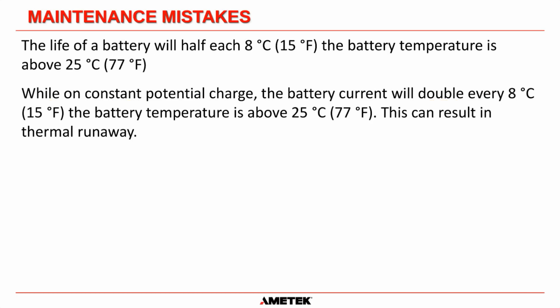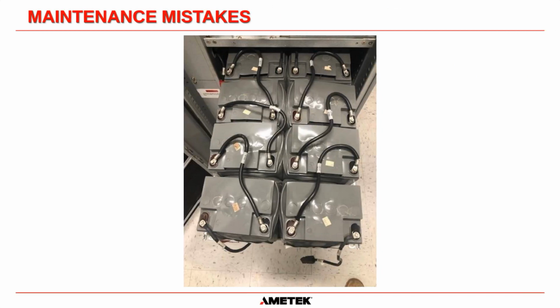And we couldn't find a really good picture of thermal runaway, because usually the batteries are destroyed. But you can see quite clearly here, these valve-regulated lead-acid batteries have swollen a huge amount. What happens is these were going into thermal runaway. The insides were heating up so much, causing pressure and causing the plastic to melt and the jars to expand. They were lucky in this circumstance because that was found before those batteries went on fire. And those batteries could have gone on fire if it was left too long.